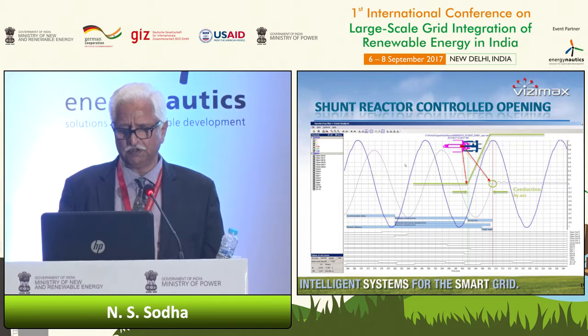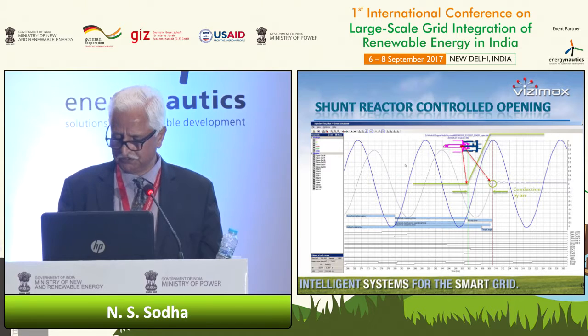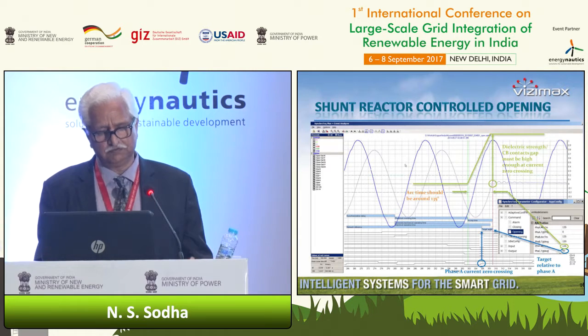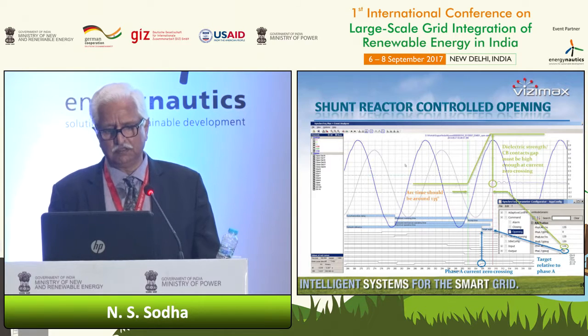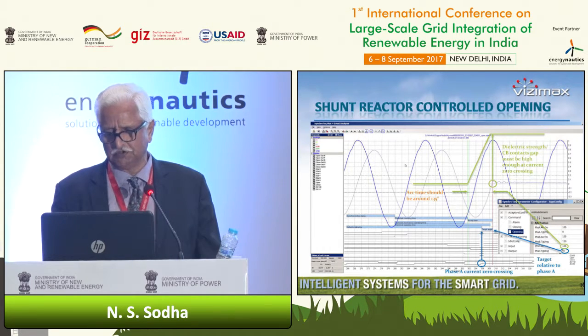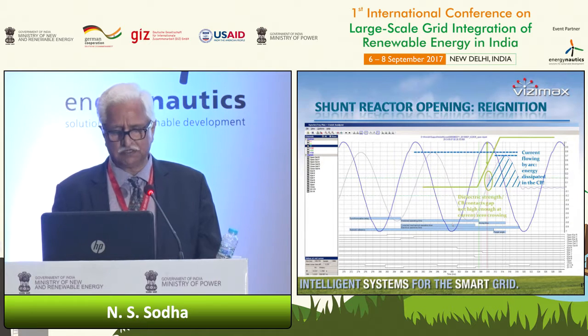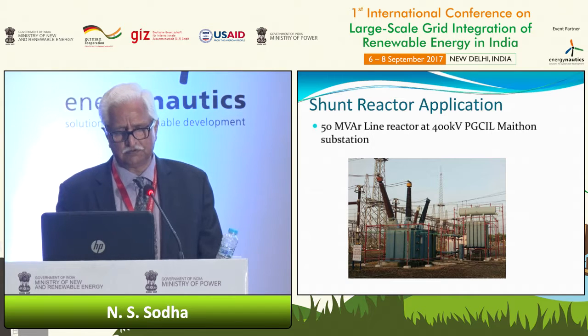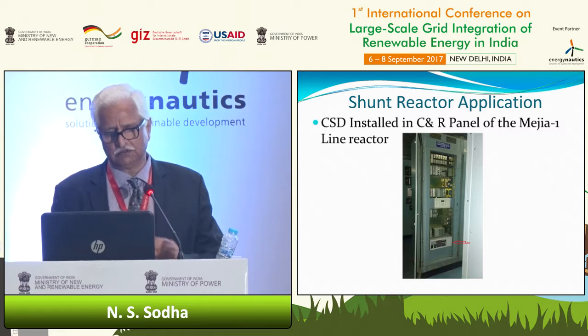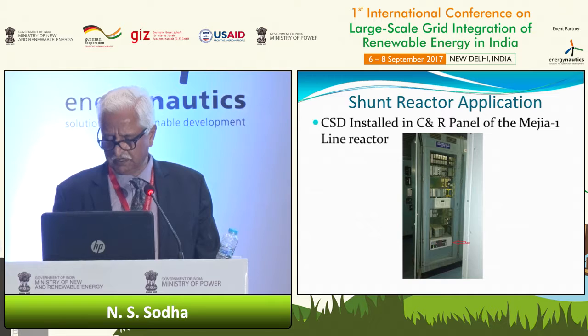Now let us see the shunt reactor opening operation, you can see the breaker contacts opening now. When it further opens, there was a strike in the contact gap, and then it is fully opened, and the situation has now improved. So what we need to do is that for control switching, particularly for the shunt reactor opening and for the transformer closing, switching on, we have to see that the control switching breakers are available. And this application was put on 50 MVAr line reactor at 400 kV Maithan substation of Power Grid. And you can see that the equipment, the CSD, control switching device, can very easily be put on the control panel as a retrofit.